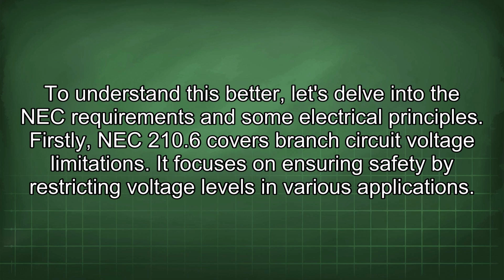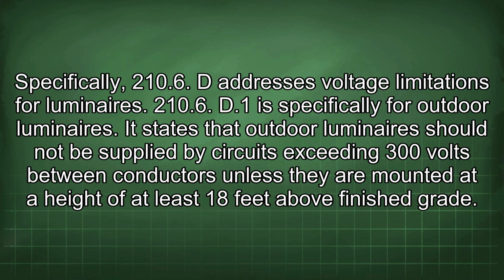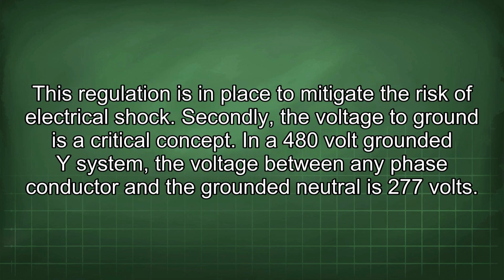Firstly, NEC 210.6 covers branch circuit voltage limitations. It focuses on ensuring safety by restricting voltage levels in various applications. Specifically, 210.6(D) addresses voltage limitations for luminaires. 210.6(D)(1) is specifically for outdoor luminaires. It states that outdoor luminaires should not be supplied by circuits exceeding 300 volts between conductors unless they are mounted at a height of at least 18 feet above finished grade. This regulation is in place to mitigate the risk of electrical shock.